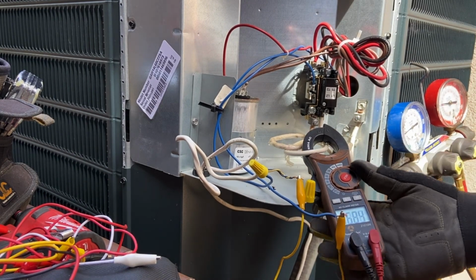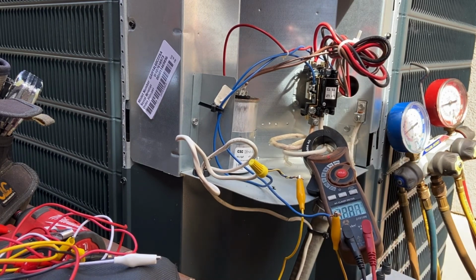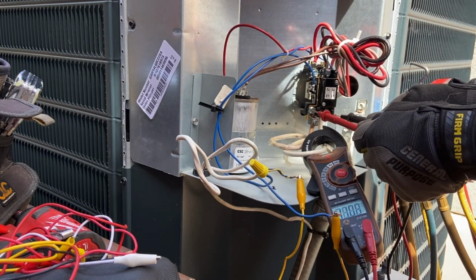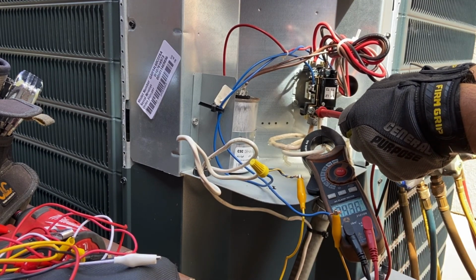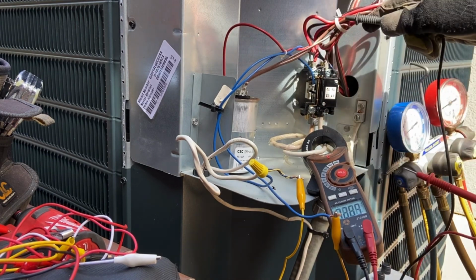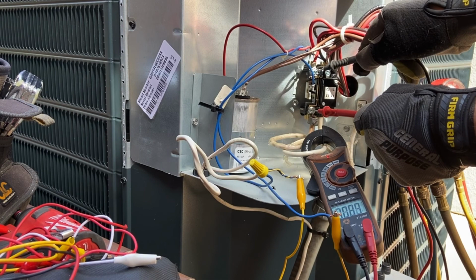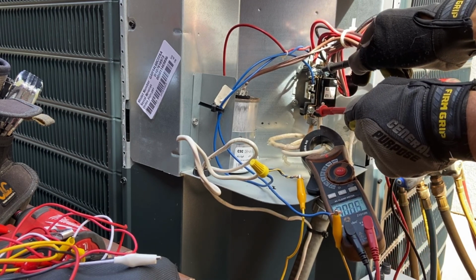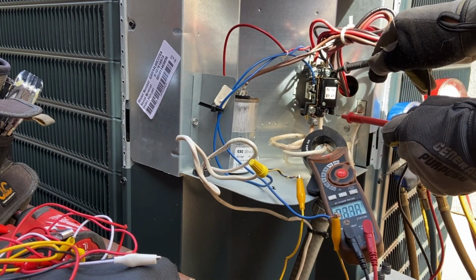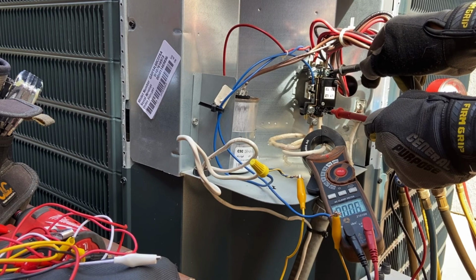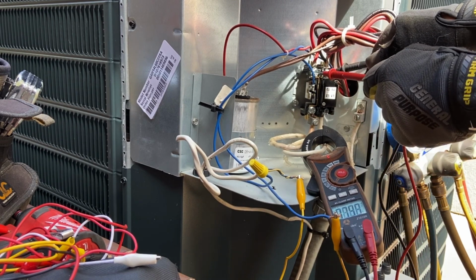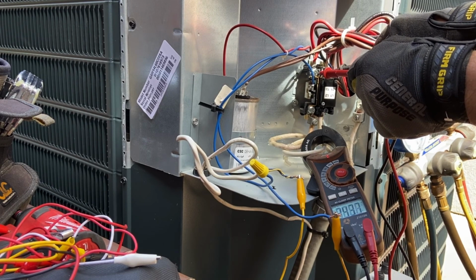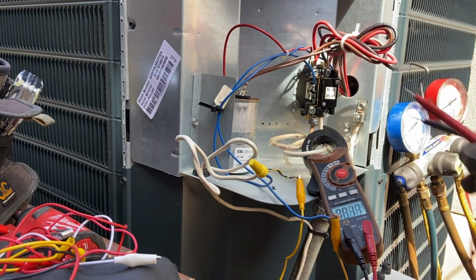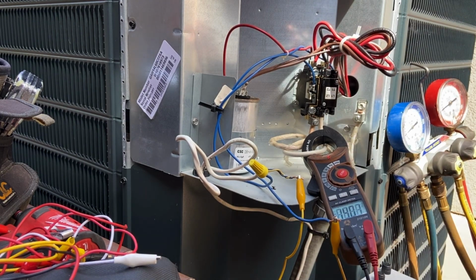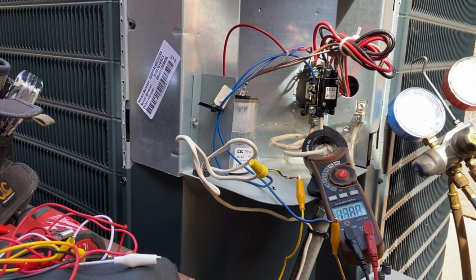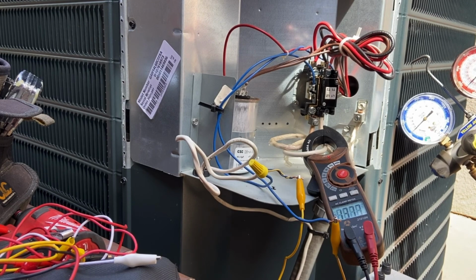I can also change to voltage on the fly. Take my meter probes: 243 volts. This being a contactor, I can check both sides on L. Let's see, that's L2. Should be 0 voltage difference. Check my other side. Across the closed contact, it's also 0, so I know that's operating right. So my voltage at the outlet of my contactor should be about 240 also. Should be the same voltage going in, going out. Okay? Go back to amperage. Verify my amperage is doing okay. I can check my gauges at this point, verify pressures, superheat, subcooling, etc.